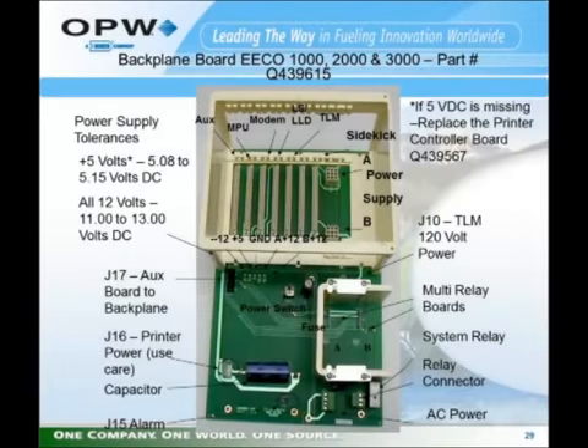The EECO 2000 works with a main board, backplane board, and a card cage where all the other circuit boards will plug into slots on the card cage. While you see that some of these slots are labeled, the slots in the card cage are essentially identical. You're not locked into plugging a certain board into a certain slot. You have some leeway in where the boards are installed in the slots, depending upon what cables are connected to the boards, usually installed to give you the least amount of interference.